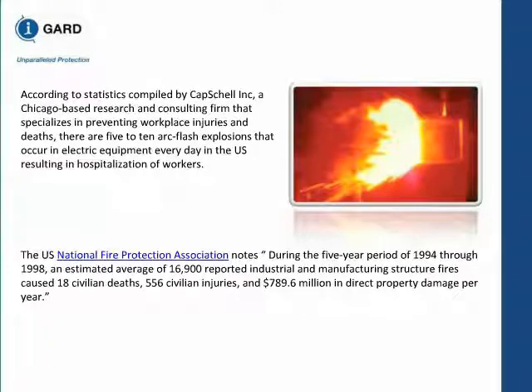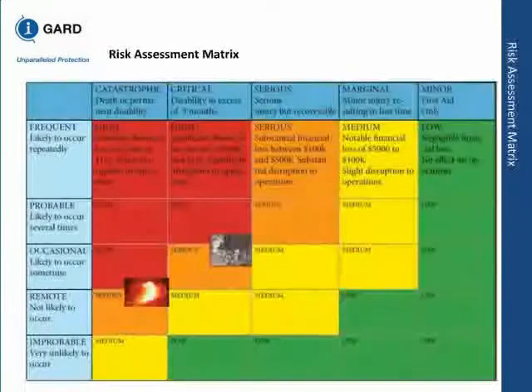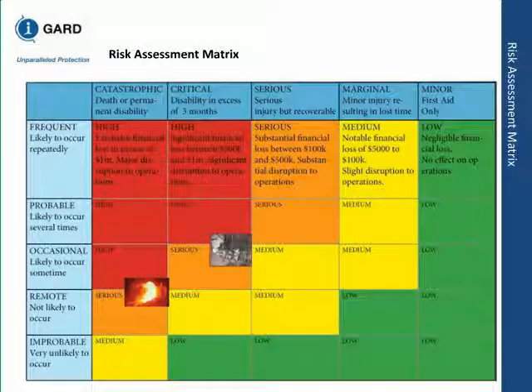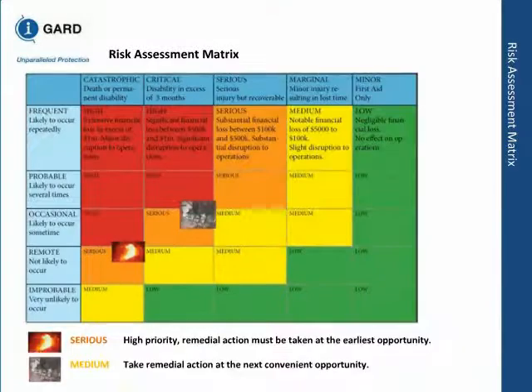Again, looking at the risk assessment matrix, if this is catastrophic or critical, you see some red blocks. Red blocks mean nobody should be working on it. If it's orange or yellow, then you can take some precaution, because the goal is that you can do work very safely. If you cannot do work safely, you do not want to do that work. It's the same matrix you see for the serious injury. It's a high priority. Remedial action must be taken at the earliest opportunity, as sometimes you notice some hazards while you were doing the work.